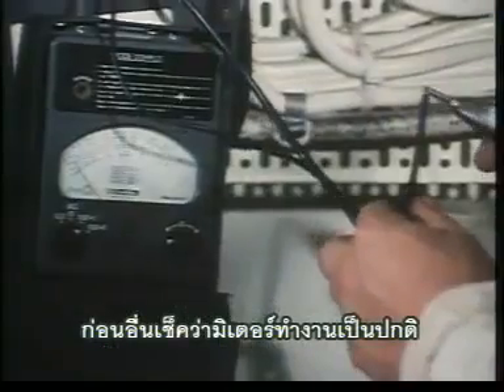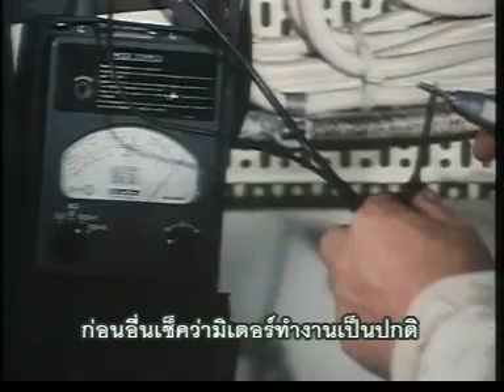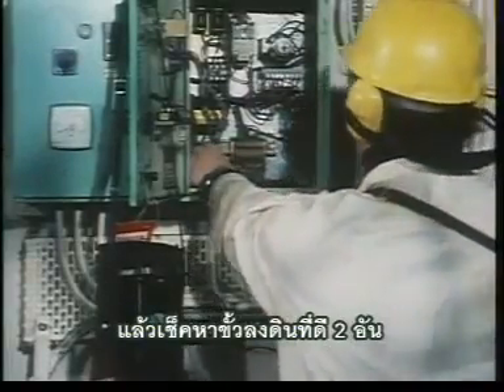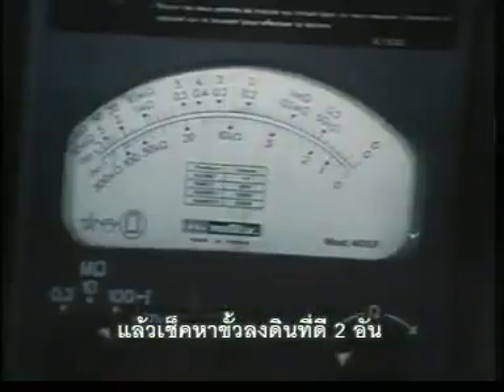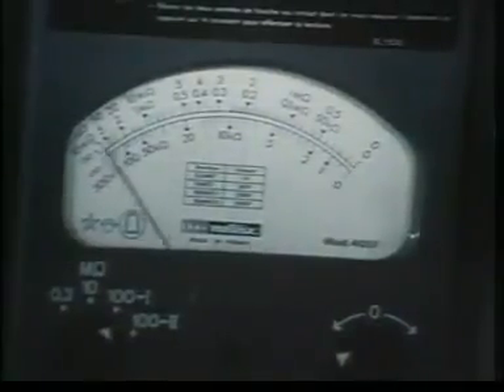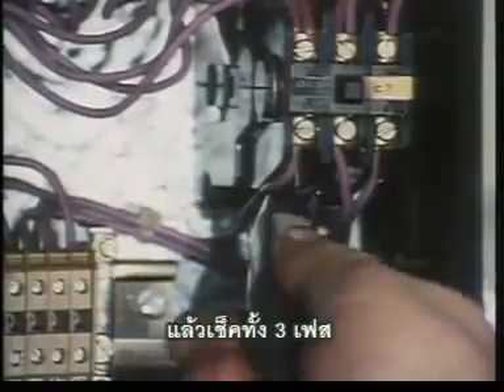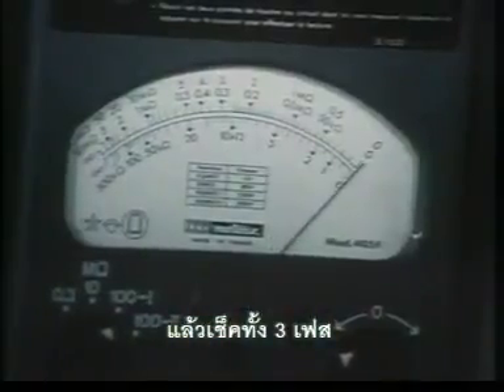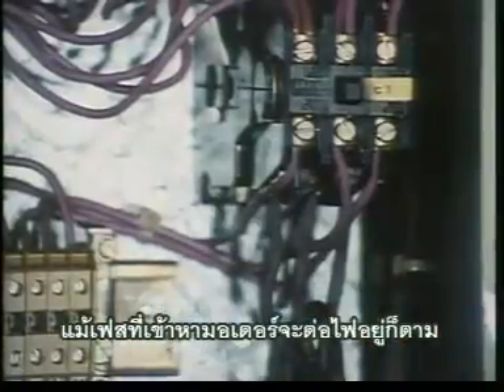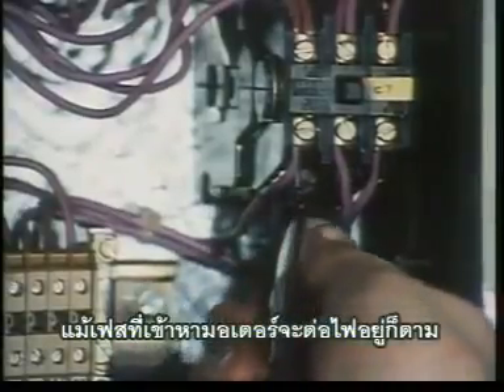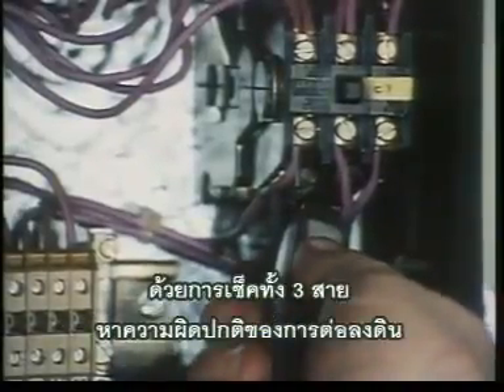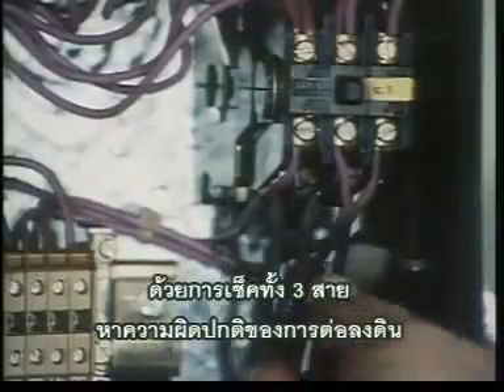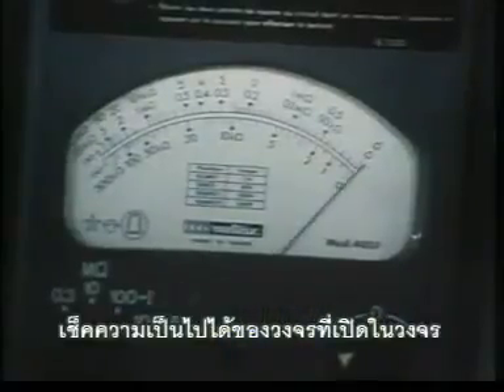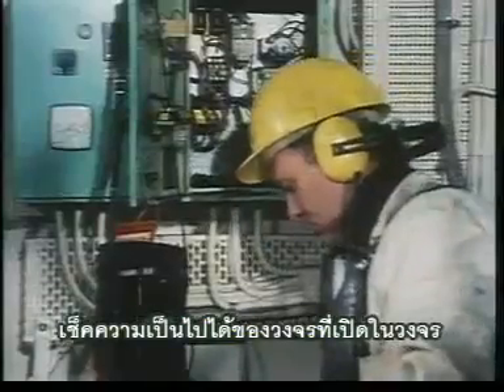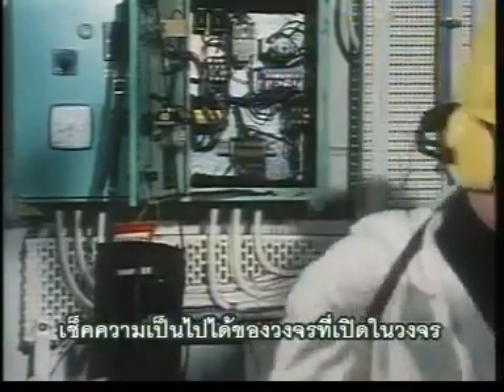First, check the meter for correct function. Then check for 2 good earths. Then all 3 phases should be checked, even though the phase windings in the motor are electrically connected. By checking all 3 cables, finding the earth fault on all 3, you have checked against the possibility of an open circuit fault on that part of the circuit.